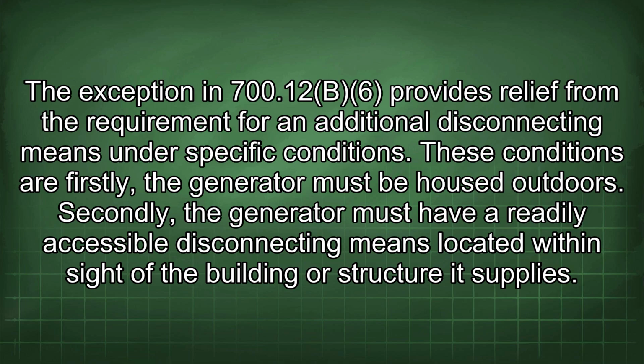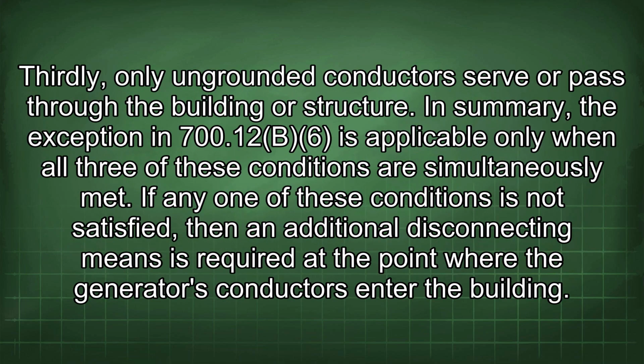These conditions are: firstly, the generator must be housed outdoors. Secondly, the generator must have a readily accessible disconnecting means located within sight of the building or structure it supplies. Thirdly, only ungrounded conductors serve or pass through the building or structure. In summary, the exception in 700.12(B)(6) is applicable only when all three of these conditions are simultaneously met. If any one of these conditions is not satisfied, then an additional disconnecting means is required at the point where the generator's conductors enter the building.